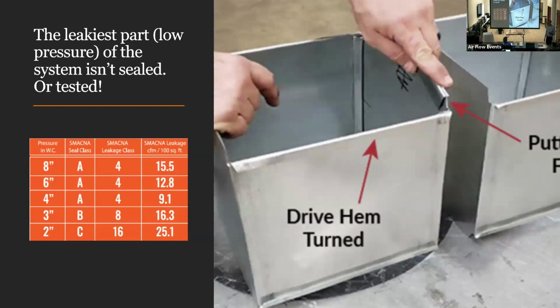Well, if you know what's going through your terminal device, and then after you do the TAB, you know what's coming out of all your outlets. And then if the balancer can somehow get that number within 10%, we're good. Is 10%, that's just downstream of the VAV box. Is 10% of your system leakage good? It's not that good. Really not that good.